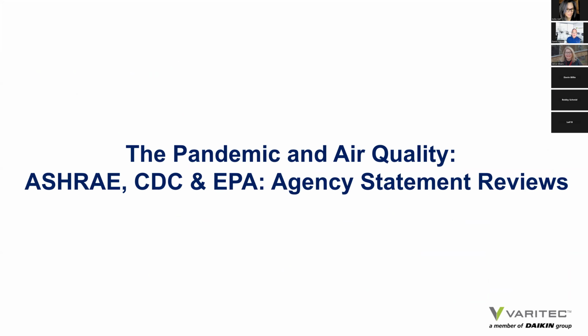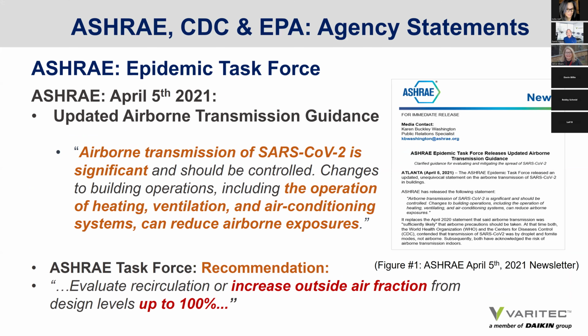So let's begin. Let's look at the pandemic and air quality, and ASHRAE, CDC, and EPA statements on both topics. First of all, I want to walk back in time to give some sense of history to this whole presentation. We're going to look at ASHRAE's April 5th, 2021 newsletter announcement that acknowledged categorically that airborne transmission of SARS-CoV-2 is a serious concern, and that the operation of heating, ventilation, and air conditioning systems can reduce airborne exposures. And one of the recommendations in ASHRAE's epidemic task force was to increase the outside air fraction from design levels up to 100%.